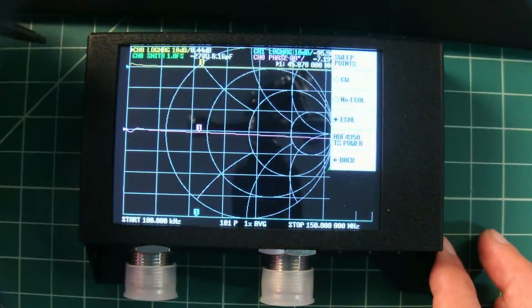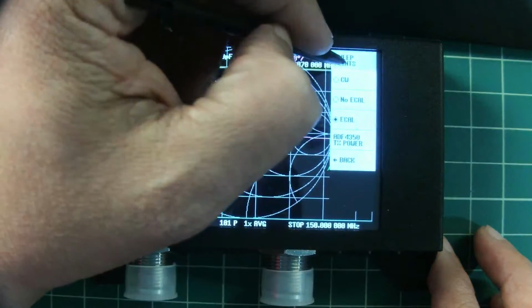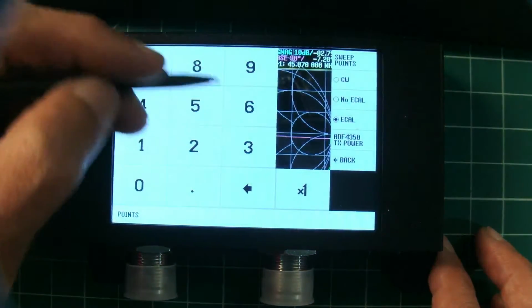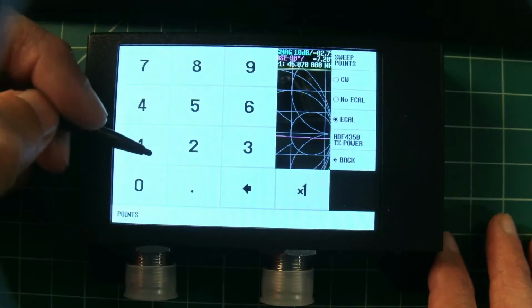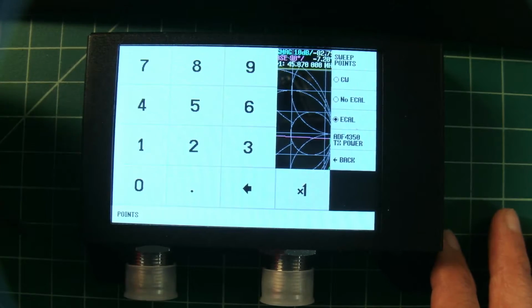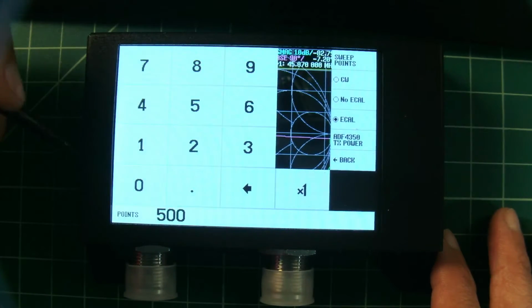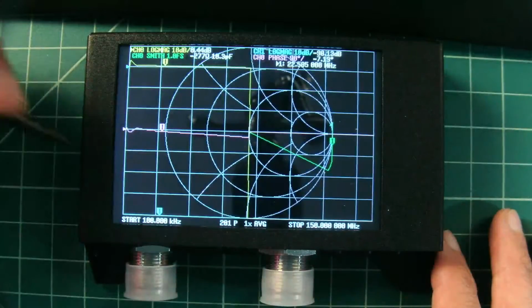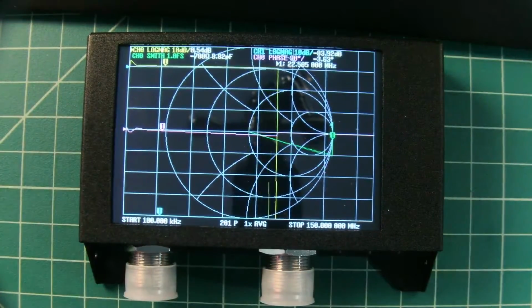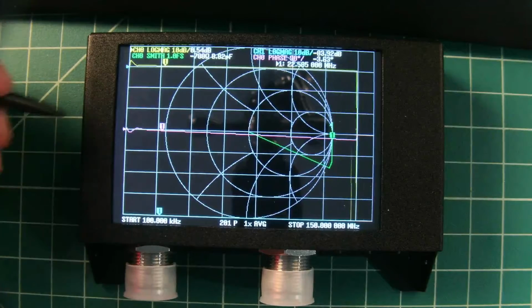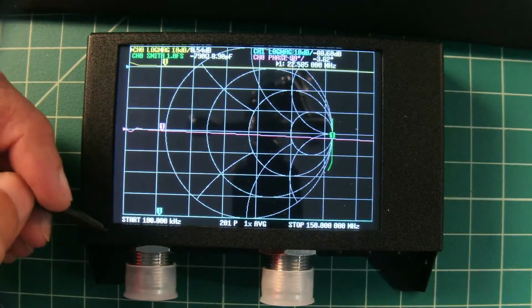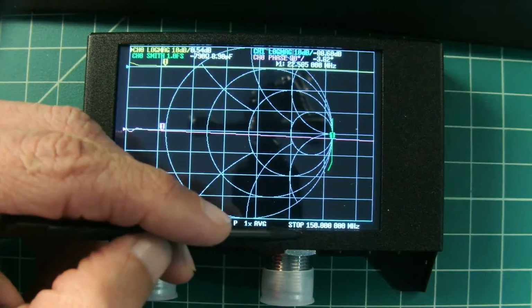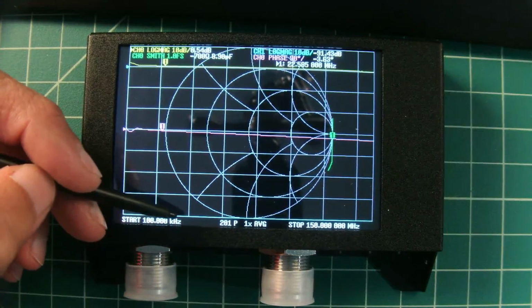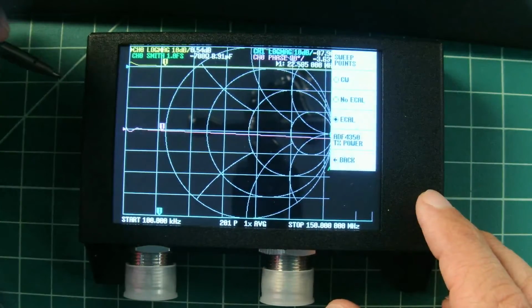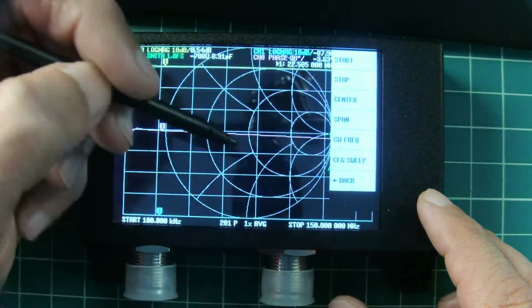And then I can go down here to configure sweep. When I turn that on, you see an option up top for sweep points. Now I can type any number I want in here, up to 201, and it will take that number. If I go above 201, it's just going to default to its max value of 201. So what we've just done is configured a sweep to start at 100 kilohertz, sweep to 150 megahertz at 201 data points.